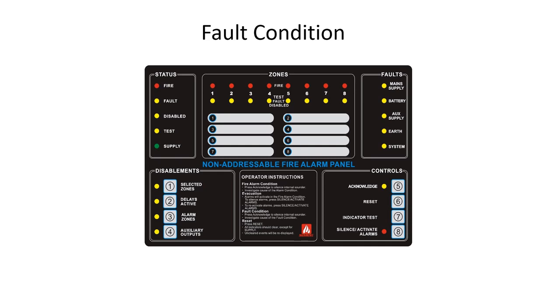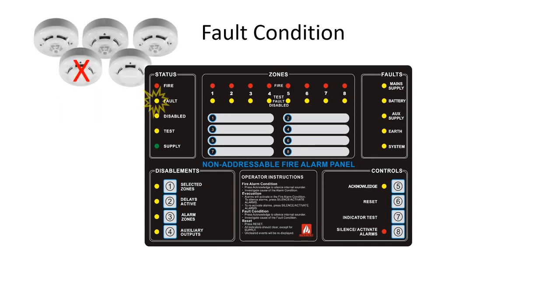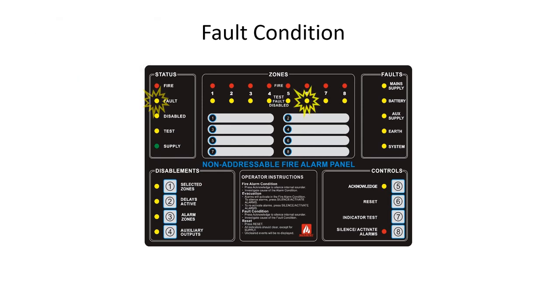In the fault condition, the panel has detected a fault in the field wiring, a connected device, or internally. The fault indicator will flash. If the fault is caused by an initiating device or zone wiring, the relevant detection zone indicator will flash. If the fault is internal to the control panel, the relevant fault indicator will flash. For either fault, the acknowledge indicator will flash together with the operation of the internal sounder.